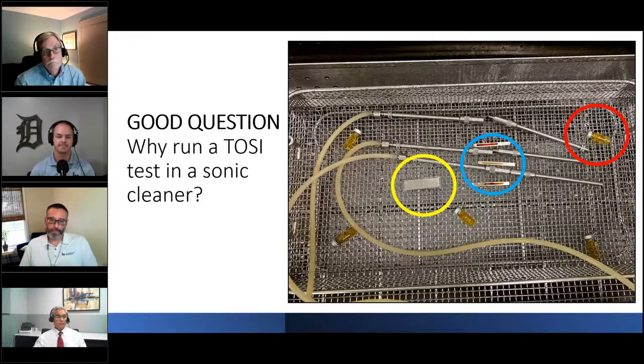So we know this machine has both adequate cavitation and is able to clean the external surfaces of instruments. Now, you may have noticed that the contents in that blue circle are our test for internal surface cleaning ability. Those coupons normally sit inside those stainless steel cannulas you see there throughout the test cycle. Hopefully you can tell pretty easily that the soil is still there.